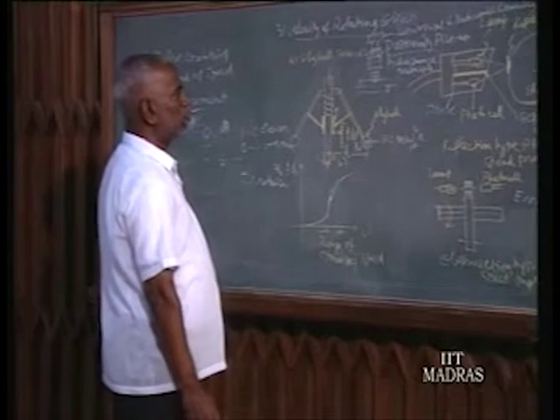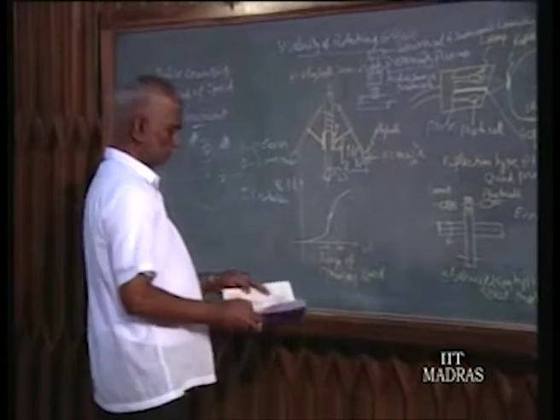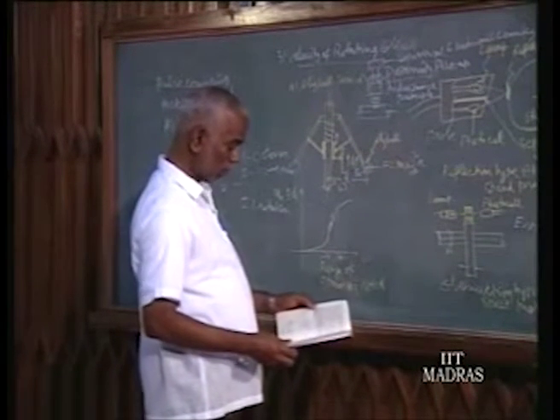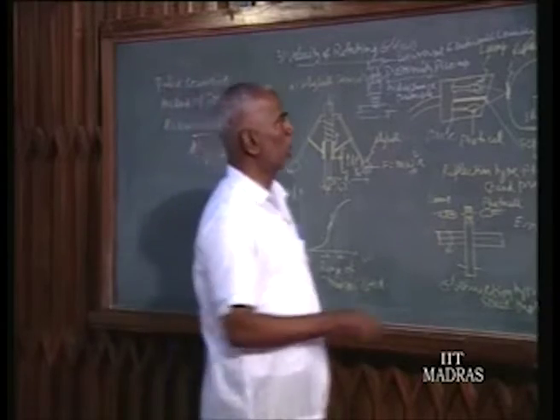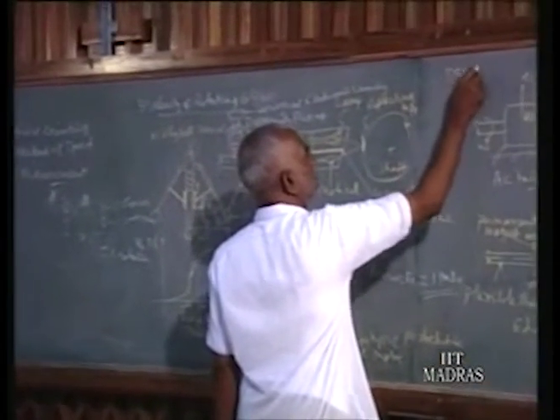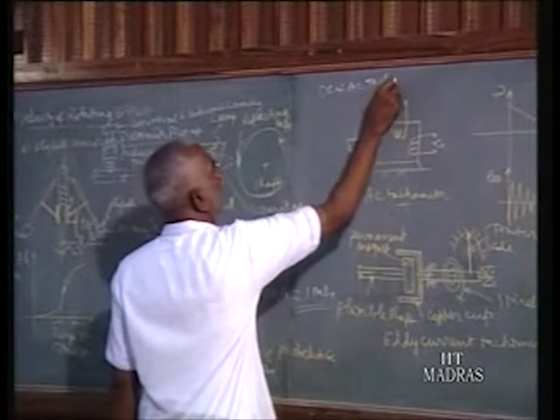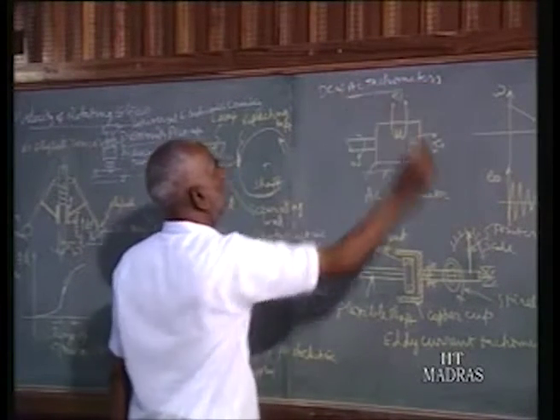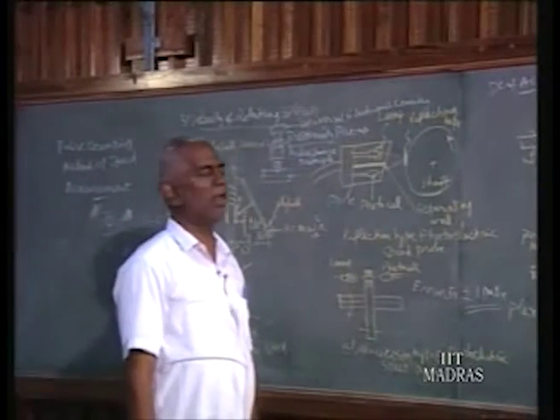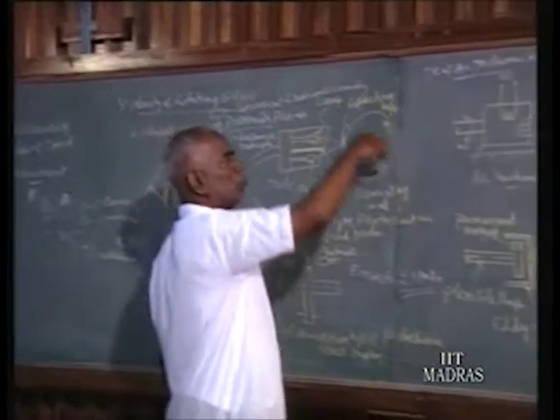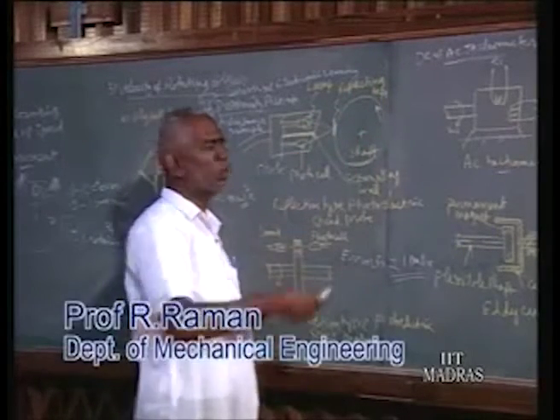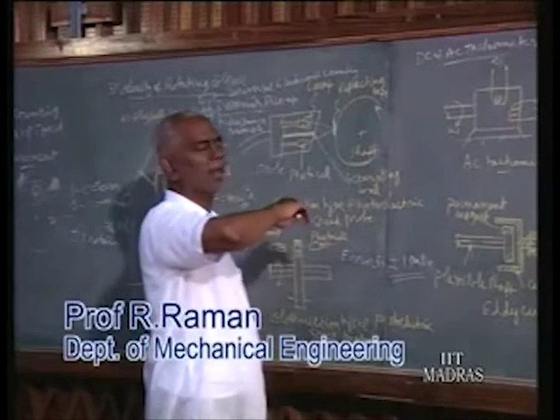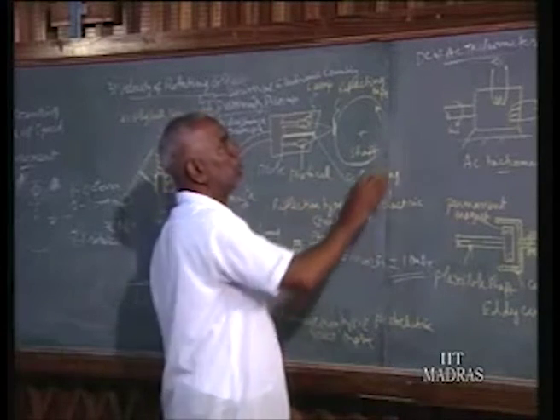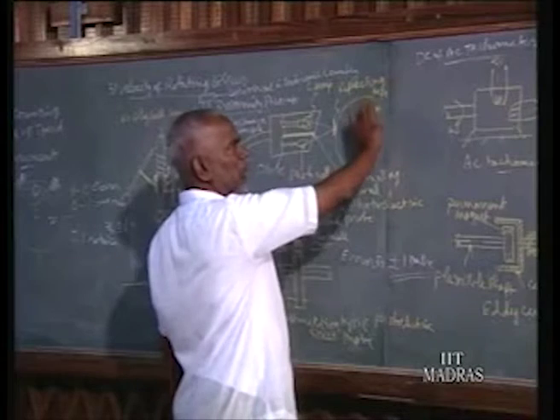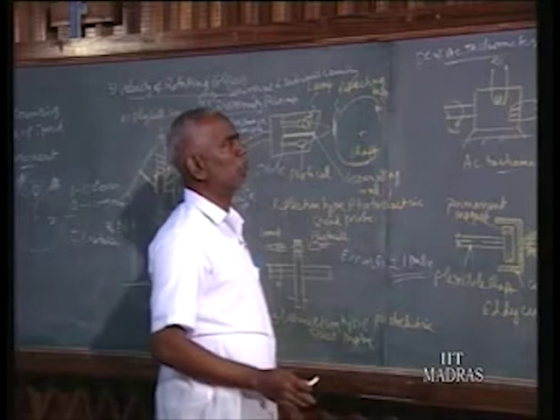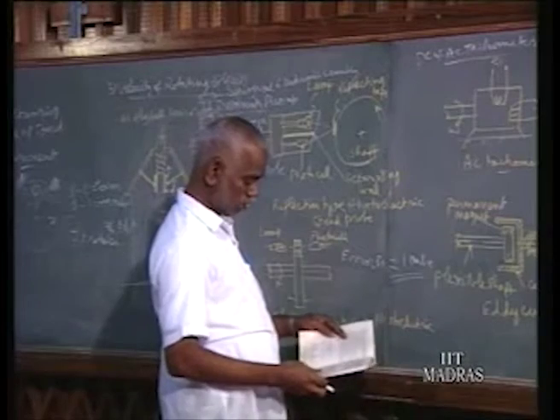So that is the pulse counting method. Next, we have DC and AC tachometers. In a DC generator, the voltage developed is proportional to the rotor speed. The voltage output of the DC generator is calibrated in terms of rotation, that is, in terms of RPM. Then it is called a tacho generator.